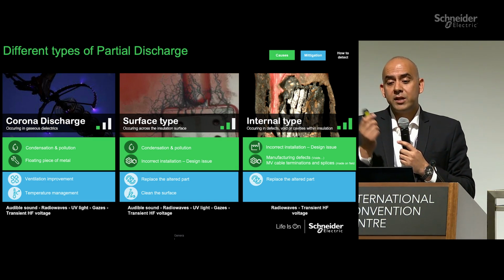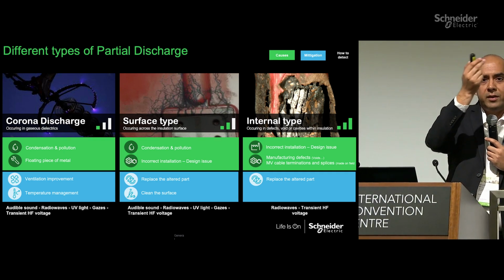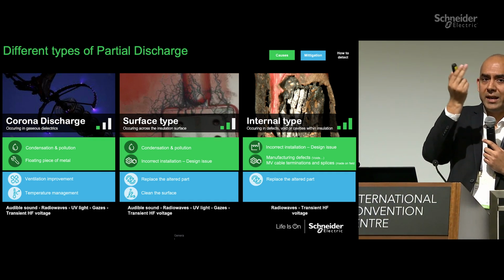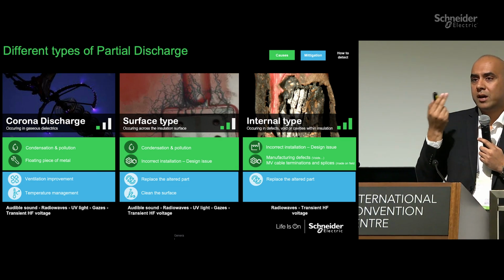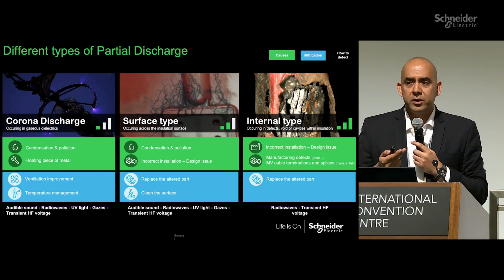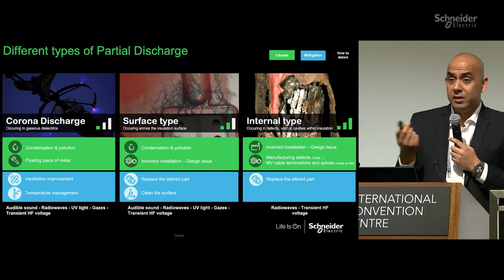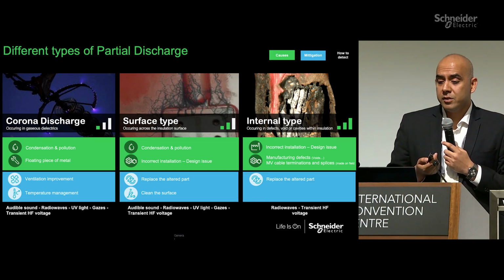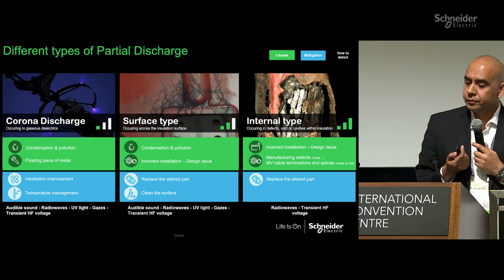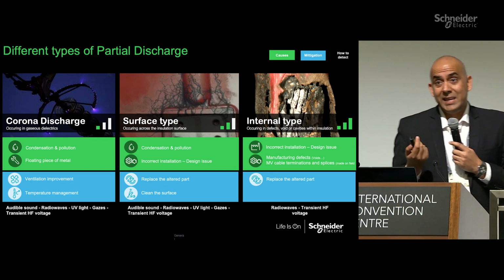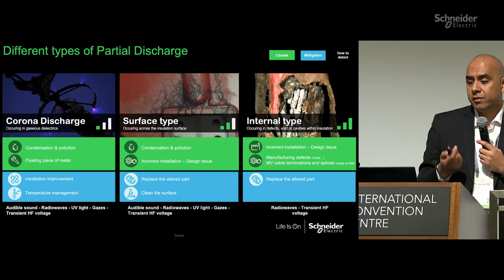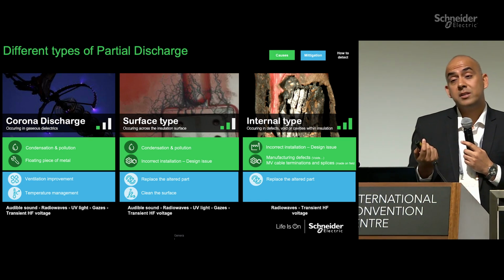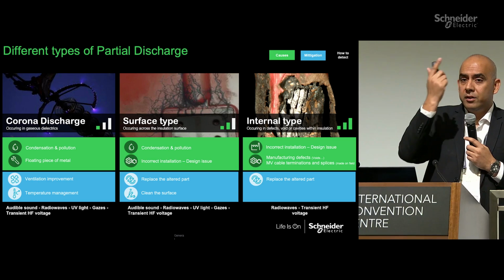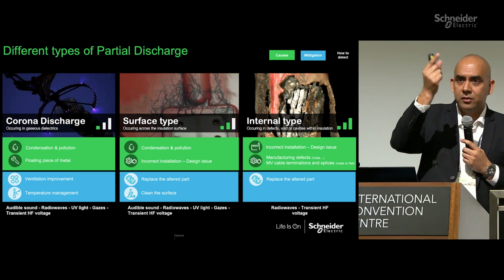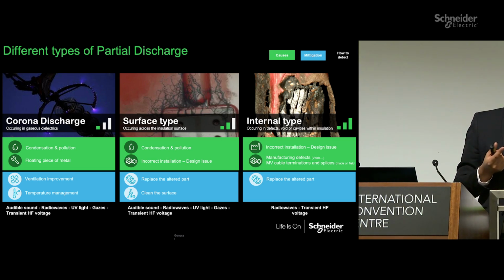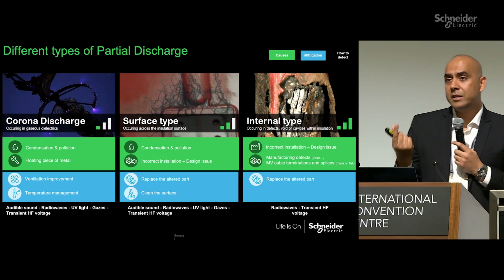Then we have the surface discharges which happen over the insulators. If there is any carbonization or dust, which could come in because of aging or normal operations, you can have this issue. And of course, the reason could be pollution, the environment could be a reason, or installation design issues which could come in. And of course, cleaning is very critical. So regular maintenance requires cleaning, and if it's not properly managed, you can see the tracks getting developed on the insulation. They damage the insulator and you have to replace the part. If you don't replace it, it can lead to a failure.